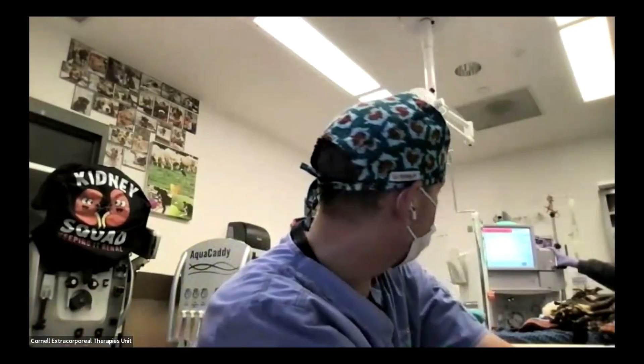They had warned us when they installed for us last year that the small circuits have an air leak detector chamber that might not be compatible, that might need some special calibration with our machine. So when we set it up a couple weeks ago, it actually worked with flying colors. And so we started using it on the small patients, and we've had a couple of really good treatments. But the first hour or so, you guys can probably see in the background there, Alicia is just pushing the mute and reset button on our pressure alarms pretty consistently. The other element of these small sets is that they don't actually have pressure lines. Well, there's one pressure line that comes off the venous side.